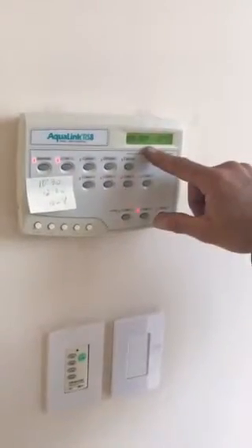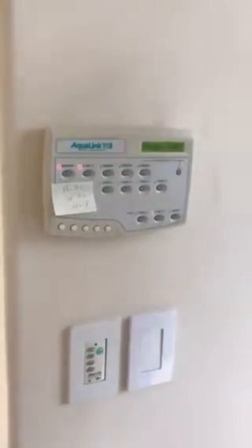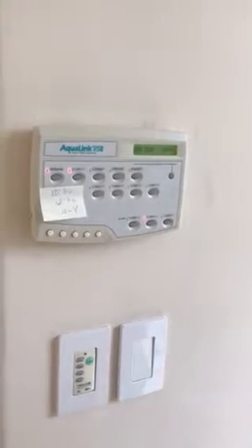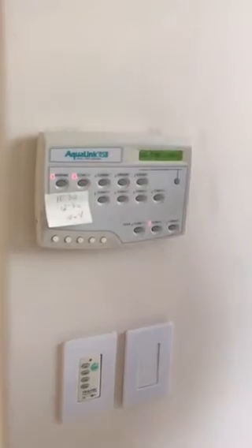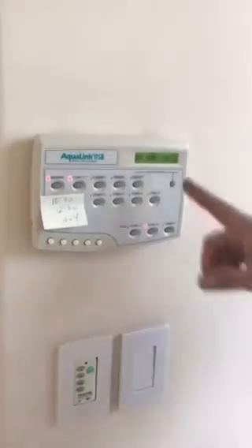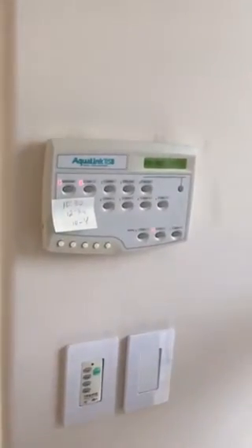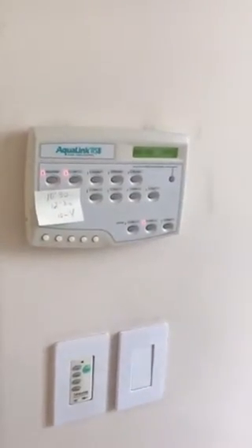It'll say pool temp. The probe is actually over there. It's not in the pool. It's just in the pipes. These valves isolate the water, and then you're heating the smaller body. But the temperature sensor for the pool and the spa is actually the same. It's just assuming that the valves worked. There's only one temperature probe, so don't think that it's over there. There might be a 1 degree difference because of the distance. It might be a little bit cooler than it actually is because it's measuring at the equipment. That makes sense.